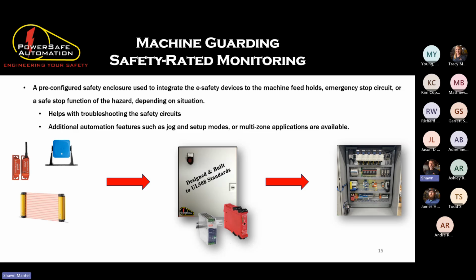What we do with this is it's a pre-configured enclosure so that it's not going inside your machine controls. We recommend a pre-built enclosure for a couple of reasons. One, it's for better troubleshooting. When you have an issue with a safety circuit, you go right there. Number two, these are typically low voltage. Most of the devices today run 24 volts, or you have 110 coming into the box. Then you don't have to worry about getting into your control box that could be running 480 inside that box and need extra compliance with arc flash and things of that nature. So a lot of times the devices will run into this pre-configured enclosure, and then it is sent to your computer or your control panels to trigger whatever that stop behavior is.